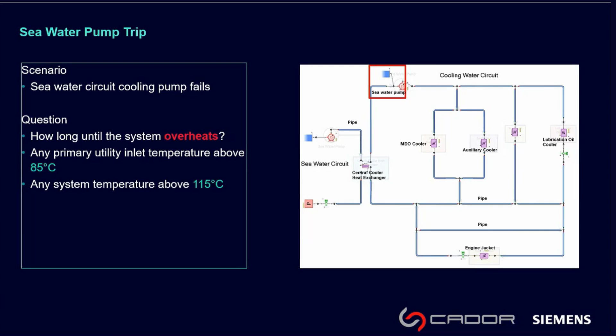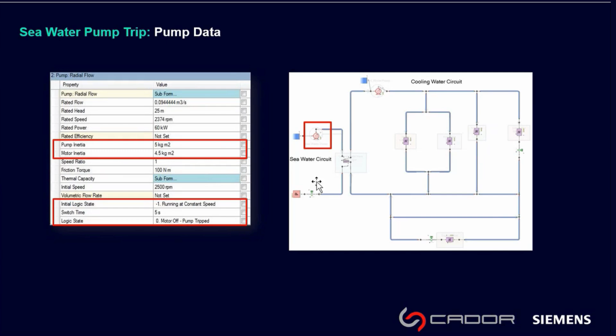So if the pump is the focus in this case, we'll be focusing on the seawater pump. What you see here on the left-hand side is the data field for the pump component. What is important to simulate pump failure scenarios is the pump inertia and motor inertia. When you switch off a pump, you would set the logic states. So initially it's running at a constant speed, and you want, let's say, at 5 seconds for the motor to shut off or trip. So what will happen? The pump will run, based on its inertia, until it comes to rest. What you are then interested in analyzing is what will be the pressure rise, for example, as a result of that, what will be the temperature rise as a result of that, and so on.